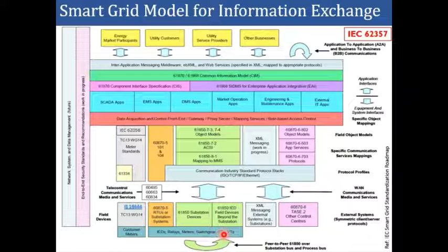Now these devices will send data via a communication mechanism to the information layer. For example, the substation devices such as intelligent electronic devices or relays will utilize the IEC 61850 protocol for binding the data. That means the data which you generate at the field will be packed into a data frame suggested by the IEC 61850 protocol.